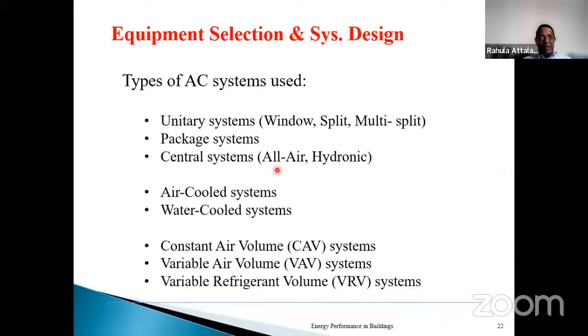These are the types. You will have the one segment, unitary systems, small units. Then you have something in between, what we call the package or the factory fitted units. And you have the central systems that are either based on water or refrigerant cooling air and air circulation, or entirely based on a water cooled system, where water is chilled and circulated through the building. Mainly, then heat rejection can take place. So that's the first category. We also have, depending on the heat rejection, air cooling or water cooling. So always water cooled heat rejection is much better than air cooling.